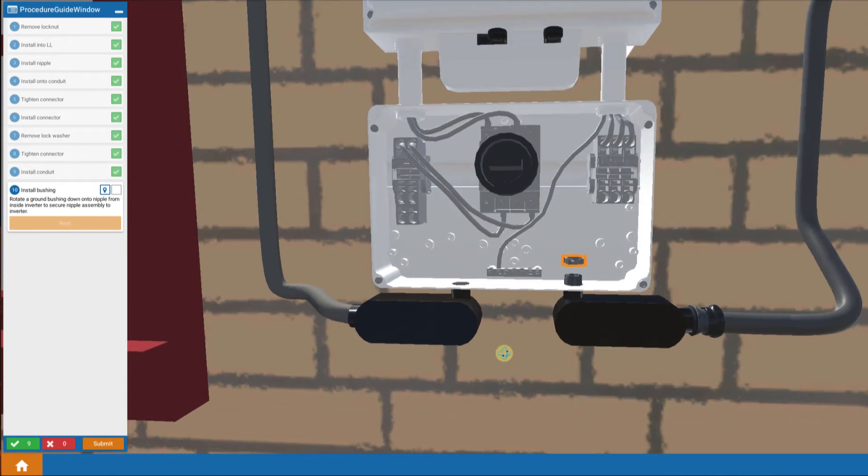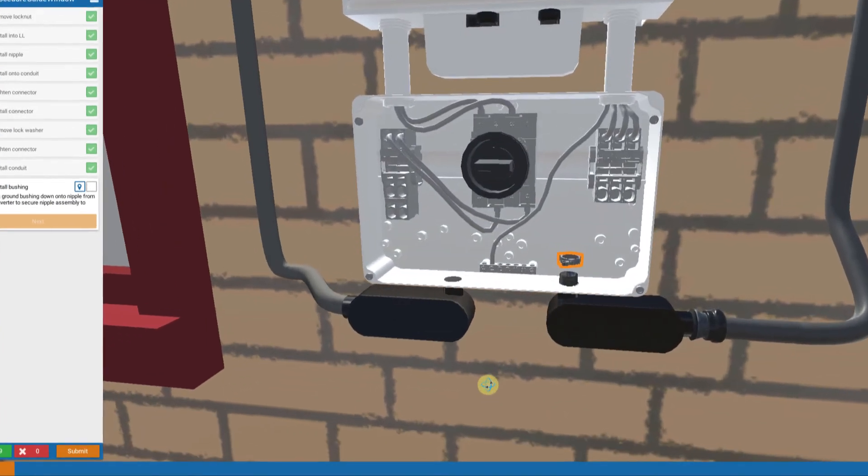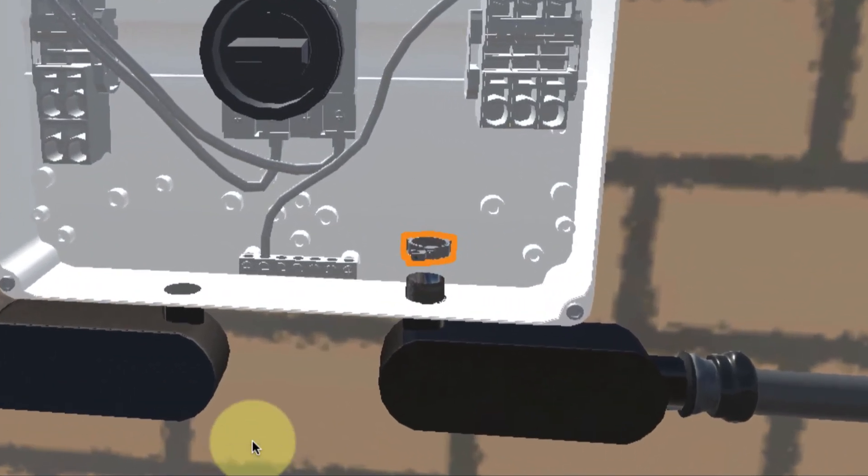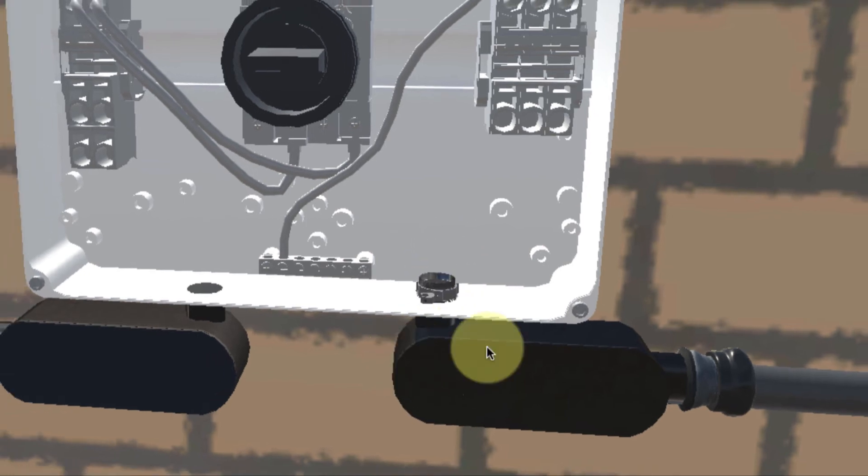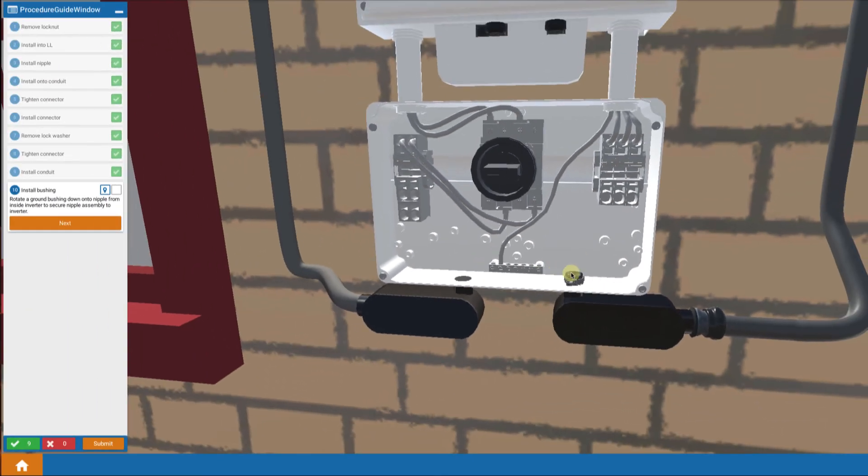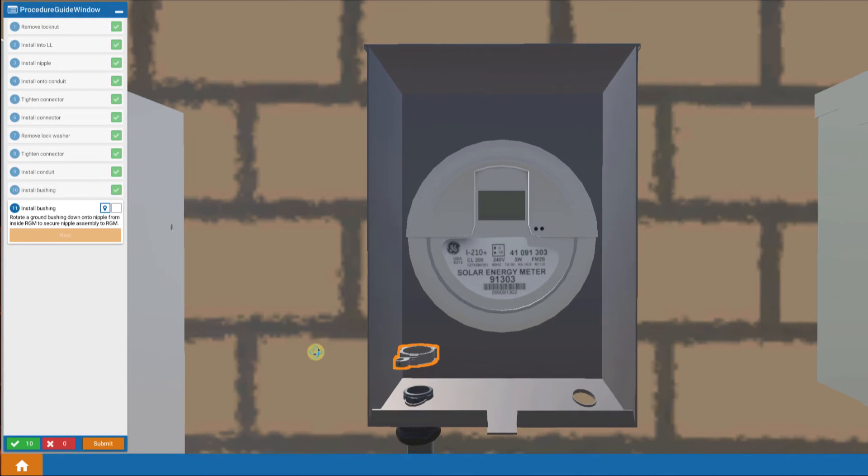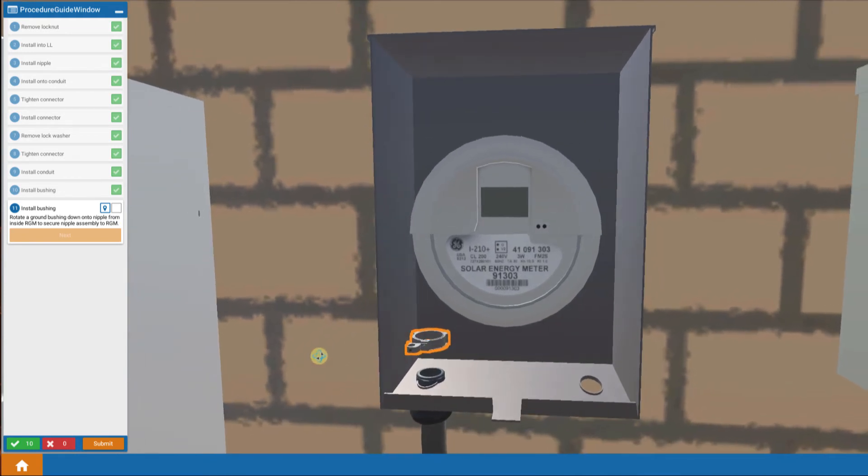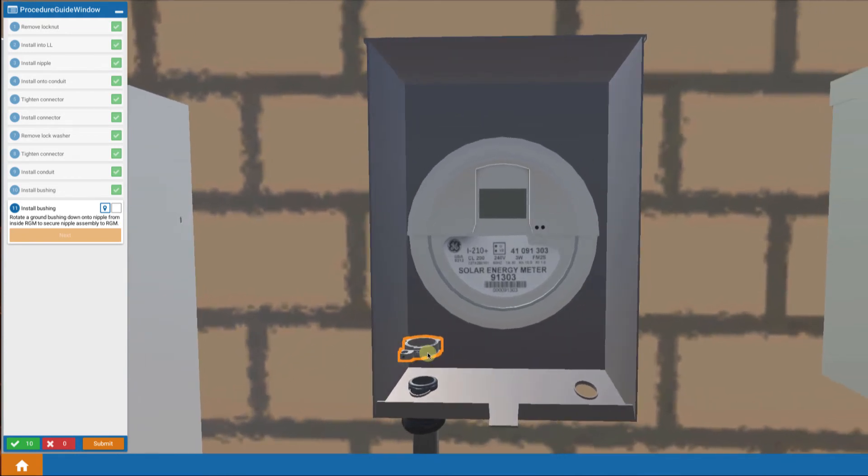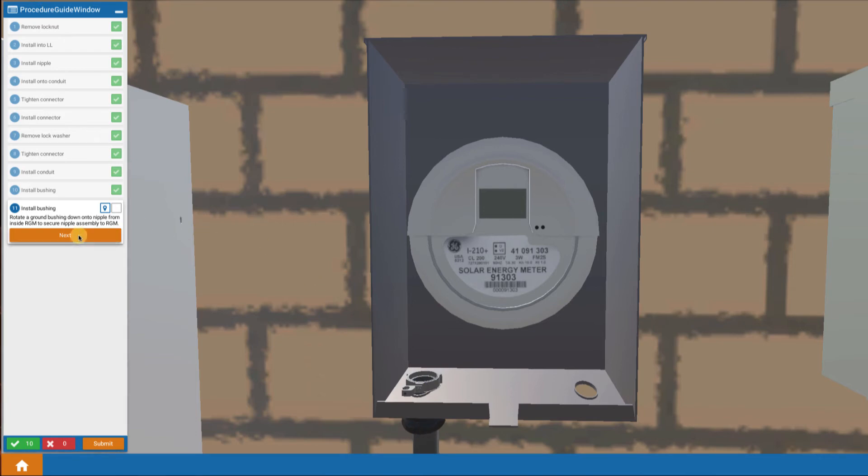Now we're going to finish by installing some ground bushings. We have a ground bushing that we're going to install down on the nipple inside the inverter and also a ground bushing that we're going to install down on the end of the conduit connector in the revenue grade meter as well.